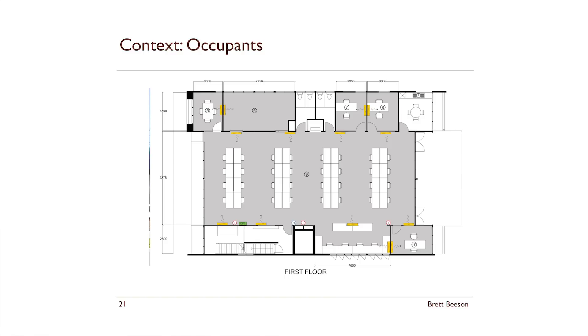So in this case, we went some way to alleviating it. So in the middle here with those four desks, we've got the majority of the staff that need to be kept cool and want to have access to the facade and to breezes. So on the west and the east, they've got access to facade. But on the north and south, they don't. So that was the best we could do in this situation, because those offices to the north block out wind coming from the north. And we did a post occupancy study as part of another research project. And we found exactly what we expected, which was in the middle, those two desks in the middle, people were really uncomfortable. So what happened is that those people were the loudest because they were the most uncomfortable. So they said, we need to close this building down and turn on the aircon. So just having 30% of the people uncomfortable, you need to try to satisfy everyone. And those 30% of people are uncomfortable. So they closed down the building. So it didn't operate in open mode as much as it could have.